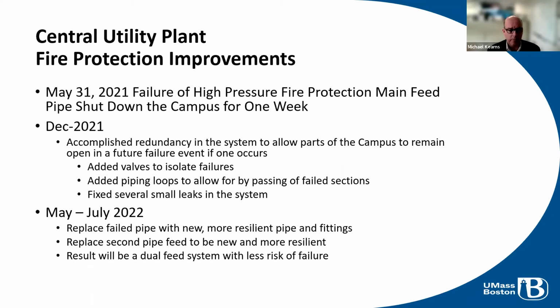So in December of 2021, we did a campus-wide shutdown when the campus was virtually empty, and we added valves and piping loops to allow for isolation. So that if we do have a failure or if we need a fire protection shutdown, we don't have to shut down the whole campus anymore. We can do it in smaller sections of the campus, which will be less disruptive to everybody.